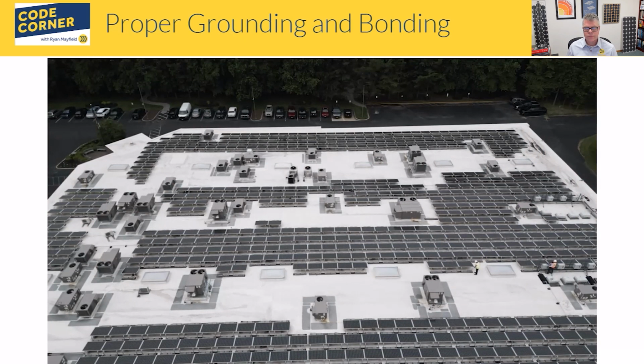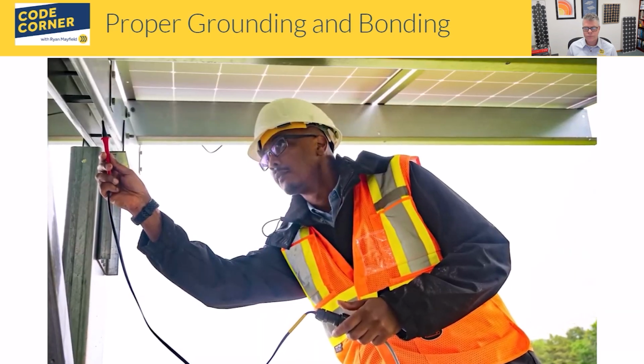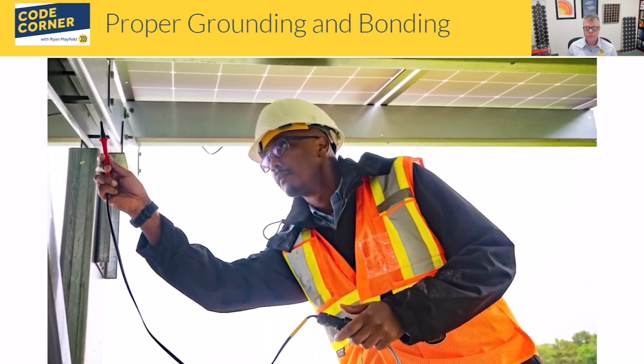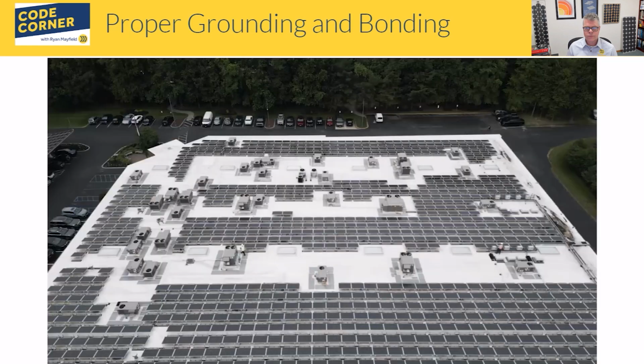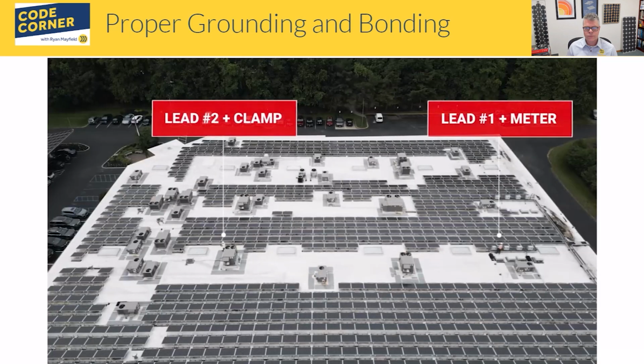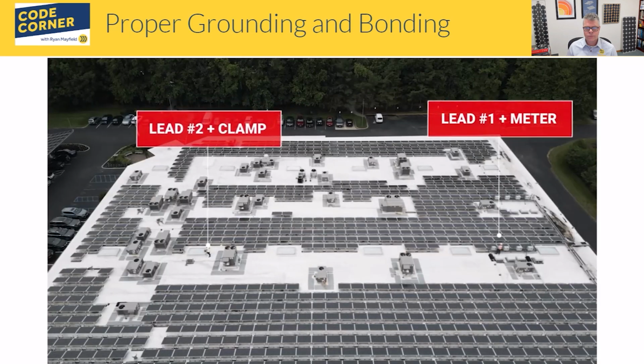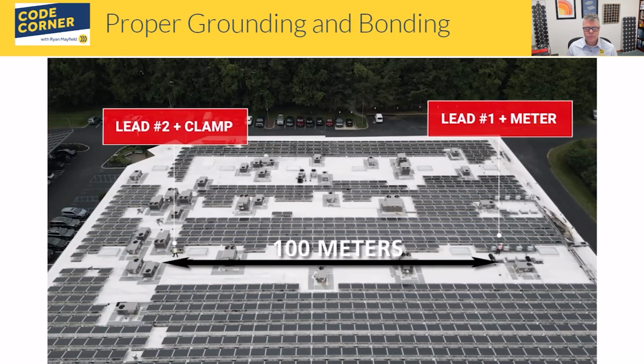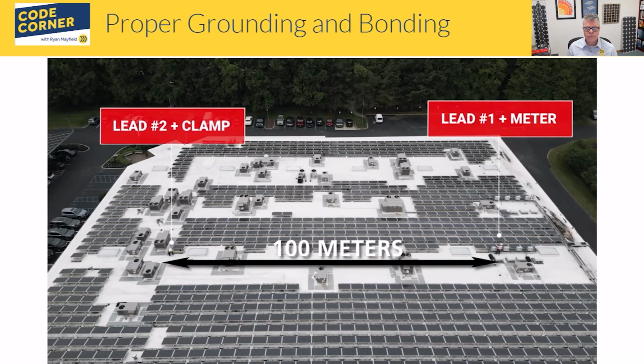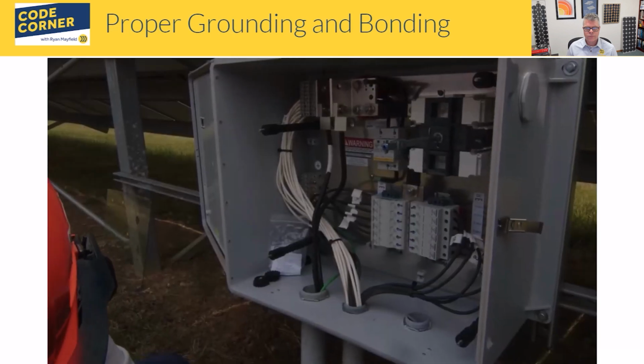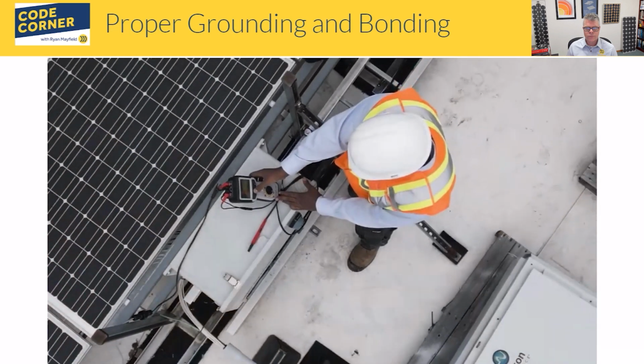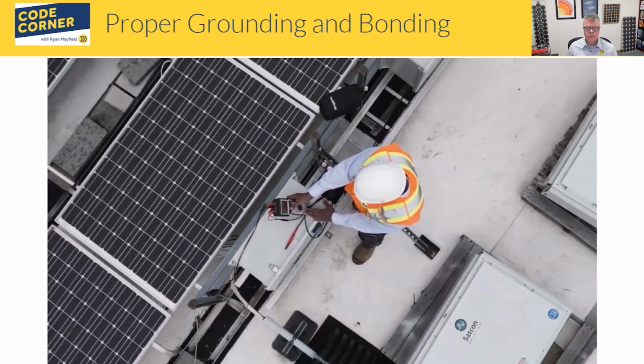A DLRO injects a small amount of current into the circuit to obtain highly accurate resistance measurements. When used in conjunction with a long test lead, a DLRO can measure continuity between remote pieces of equipment up to 100 meters apart. This test verifies proper bonding of all metallic components and ensures that the ground fault detection devices will be able to operate as intended.